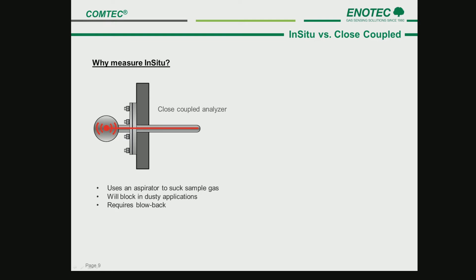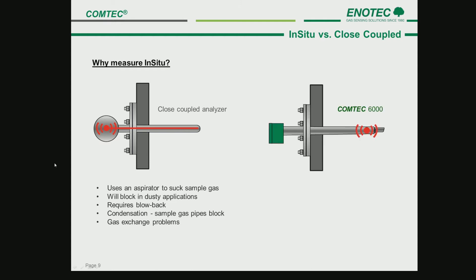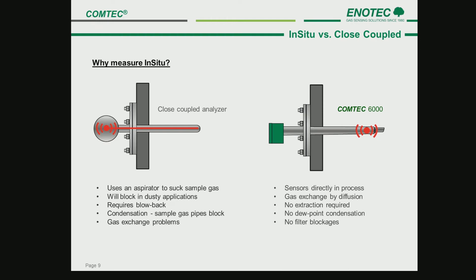The probe requires blowback systems to clear blockages. Acid condensation can take place, sample gas pipes block — especially when gas components such as sulfur are present in the flue. This leads to low sample gas flow or blockages in the sample gas pipes. The Comtec sensors are directly in the process and gas exchange takes place through large diffusion filters. No extraction is required, no dew point condensation takes place, no filter blockages occur. These simple principles make the Comtec system a low-maintenance system.